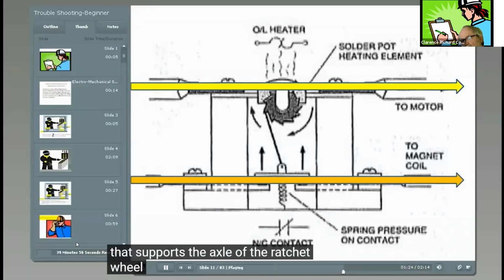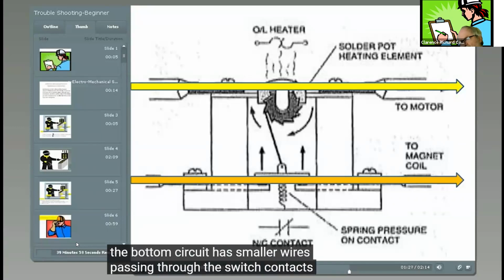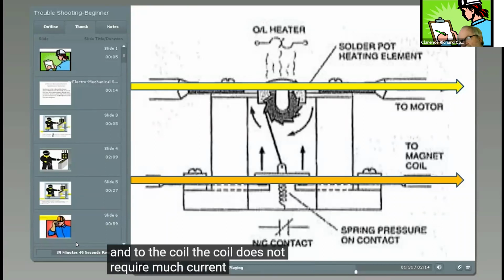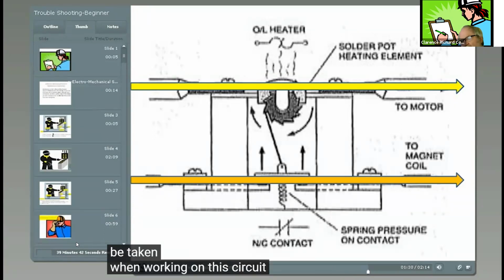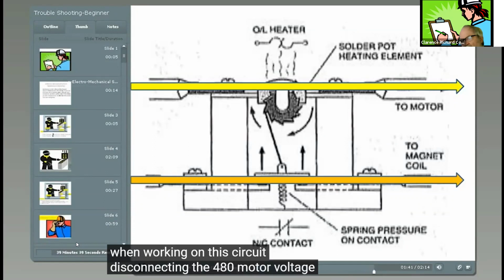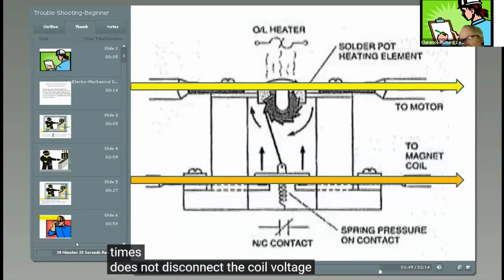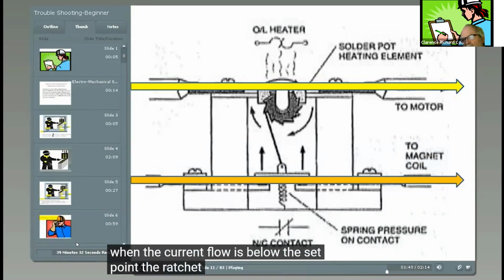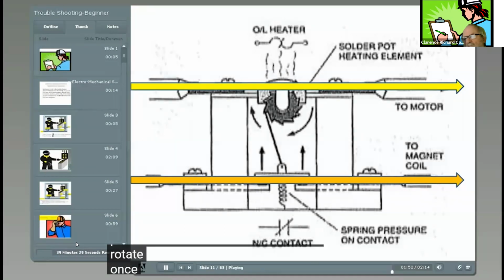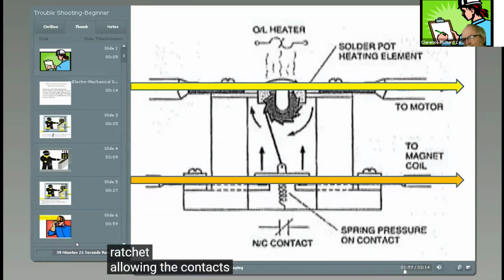The bottom circuit has smaller wires passing through the switch contacts and to the coil. The coil does not require much current to energize, therefore the wire is smaller. Care must be taken when working on this circuit. Disconnecting the 480 motor voltage many times does not disconnect the coil voltage. When the current flow is below the set point, the ratchet is fixed and does not rotate. Once the set point is exceeded, the ratchet is no longer fixed, and the spring-loaded pawl rotates the ratchet, allowing the contacts to open, and consequently the coil holding in the contactor is de-energized. The contactor is not supplying voltage to the OL relay anymore, and consequently the motor stops running and is allowed to cool down before burning up.